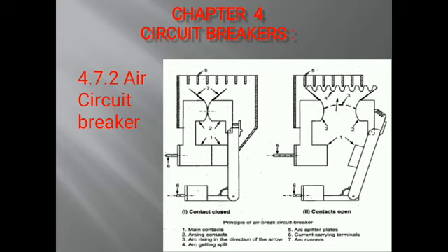In this air circuit breaker, a chamber is fitted surrounding the contact. This chamber is called as arc chute. The arc is made to drive or force in it. The arc chute helps to achieve cooling. Arc chute is made from some refractory material. Arc chute is divided into a number of small compartments by using metallic separation plates.